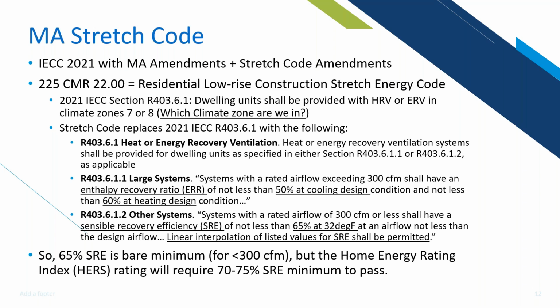But note that the 65% SRE requirement for systems under 300 CFM might be what the code calls for. But when you do go for a HERS energy rating, the home energy rating index, it will usually require between 70 to 75% SRE. And that's what I'm hearing from the field, just so you know.